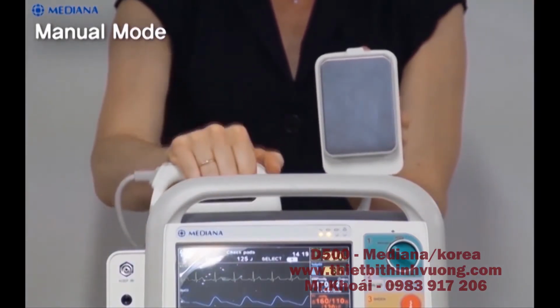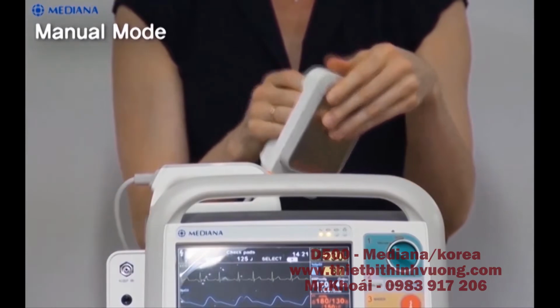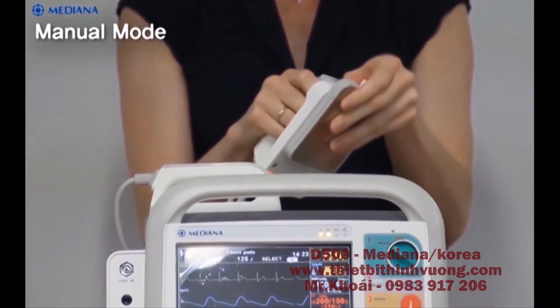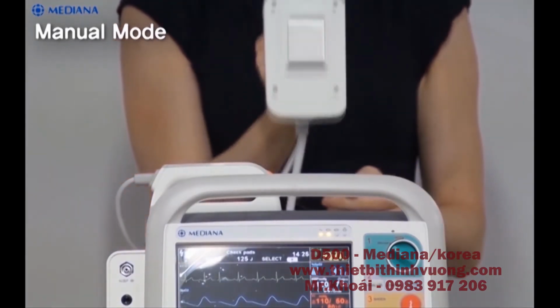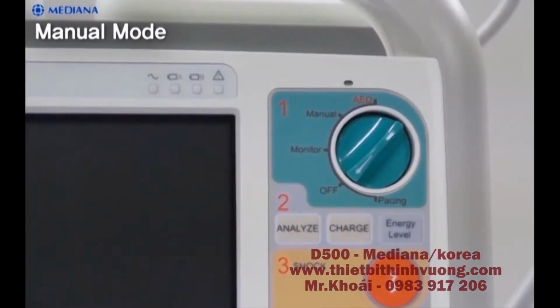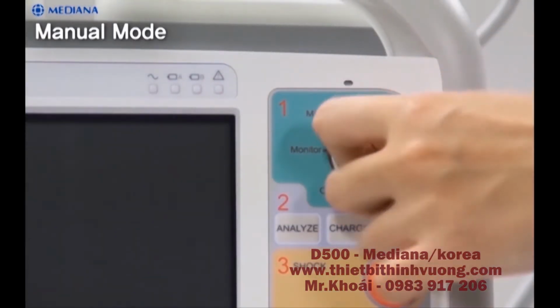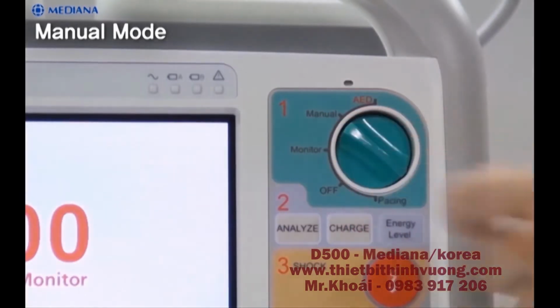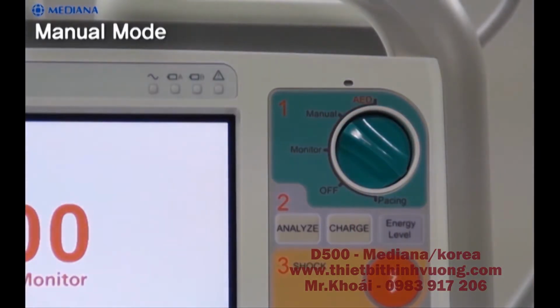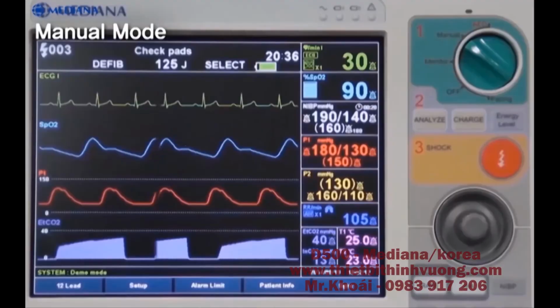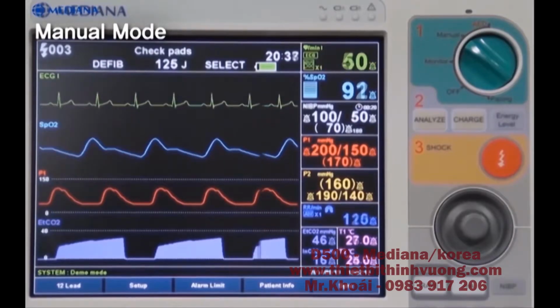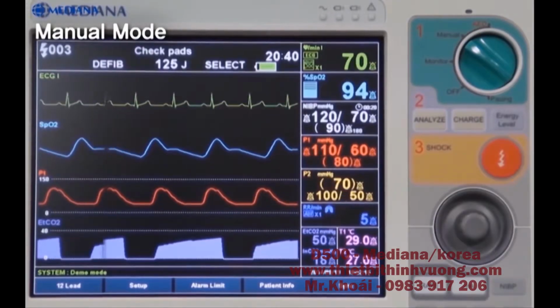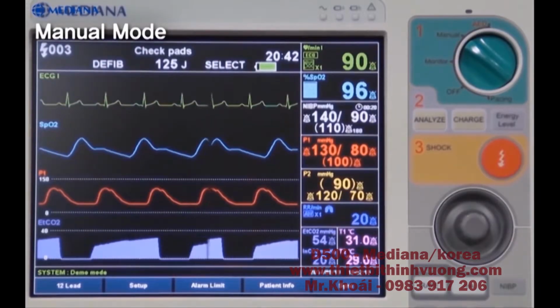If you want to use the pediatric paddles, depress the latch at the front of the external paddles while pulling forward on the adult paddle plate. Next, apply gel to the paddle electrodes. Put the paddles to the patient's bare chest and select the manual mode of the D500 by rotating the mode select knob. When the manual mode of the D500 is activated normally, the energy select display will be shown on the top of the screen and other parameter information will be displayed.